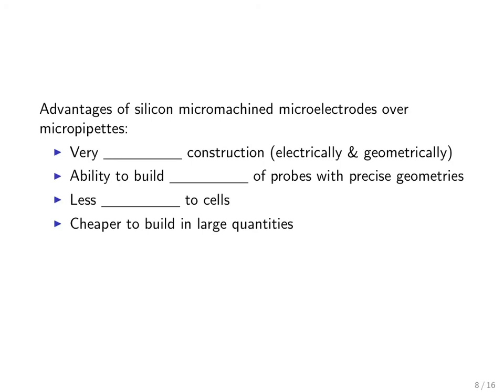So the advantages of silicon micromachined microelectrodes over micropipettes include the ability to do very precise construction. You get both precise construction electrically, so that every probe you make has the same electrical properties, and geometrically. You also have now the ability to build arrays of probes with very precise geometries. Typically, one probe that we're going to insert in the brain is not going to cut it. We need to have lots of different measurement sites. They cause less injury to cells than micropipette electrodes, and once you've set up the machinery to build one of them, building more is very cheap. So it's cheaper to build them in large quantities.